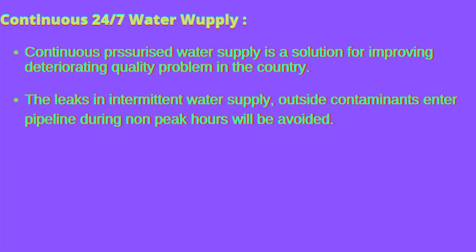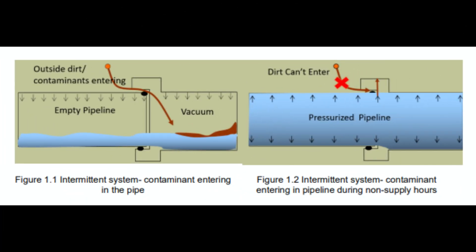Let us understand what continuous 24x7 water supply is. Continuous pressurized water supply is a solution for improving the deteriorating water quality problem in the country. Through leaks in intermittent water supply, outside contaminants enter the pipeline during non-peak hours due to the vacuum that develops inside the pipeline. Thus, water becomes non-potable.